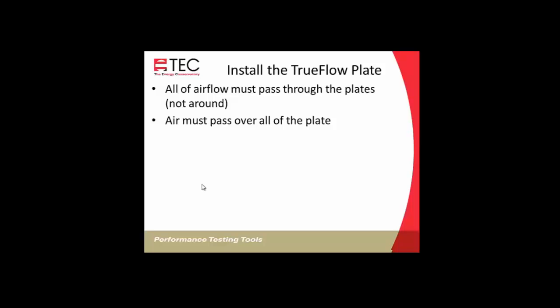So if you have a 14 by 14 register that you want to put the TrueFlow plate over, and the TrueFlow plate is 14 by 20, all of those holes don't have air passing through them. It's measuring total pressure and static pressure and averaging them over the array. And air must pass over that entire plate, not just part of it. Otherwise, it'll be including averages from locations where there's no hole, where the holes aren't seeing any airflow.